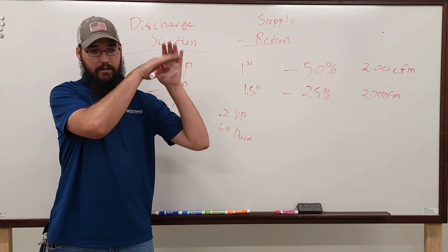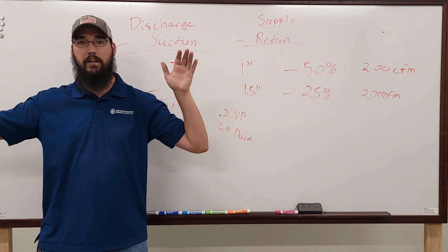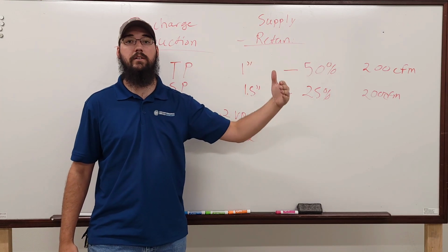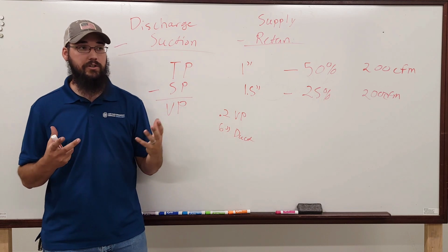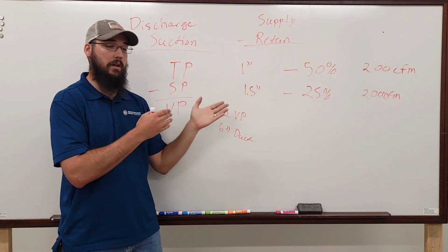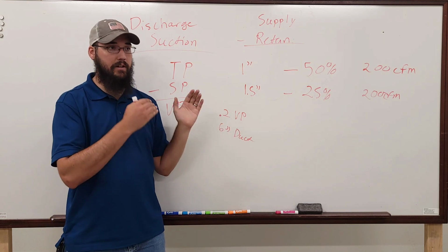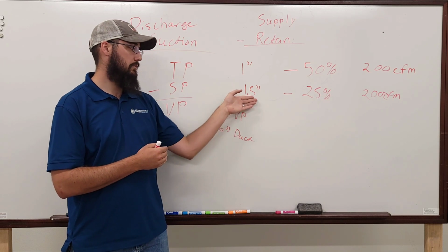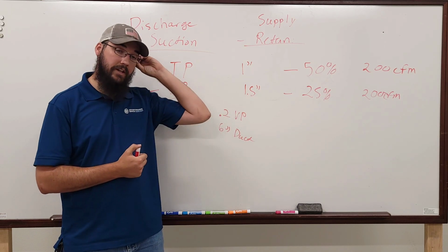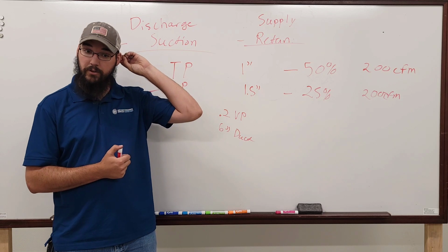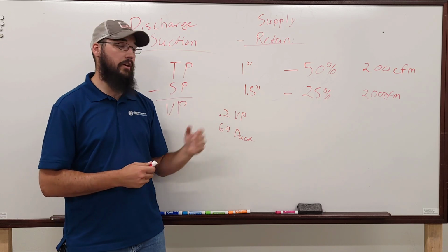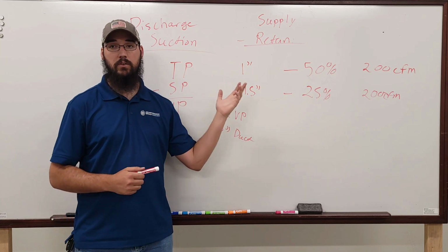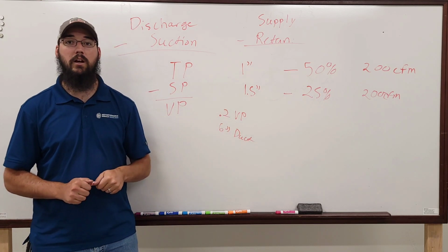It's just a domino negative. So we have to be careful not to fall into that trap. Again, our goal, our job is we're trying to protect that blower. That motor will live and die based off of these numbers. It's hard to have that conversation with the customer, but if they want 20 years out of that motor, this is how their system should be set up.